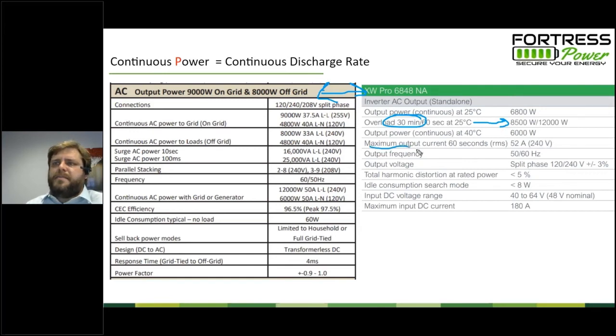If we look at this maximum output current for 60 seconds and it's 52 amps, well, a volt times an amp is a watt. So 52 amps multiplied by 240 volts will get you 12 kilowatts. So an inverter in the 6 to 7 kilowatt range can actually exceed its performance for a short duration, but it's important to note that this is not for a long duration. The minute this inverter goes above its continuous output rating, you get a little bit of wiggle room, but it's usually a hard shutoff. If you go for more than a minute above the output rating, it turns off. So it becomes very important that the loads you put on your inverter are less than its output rating to ensure good reliability and system performance.